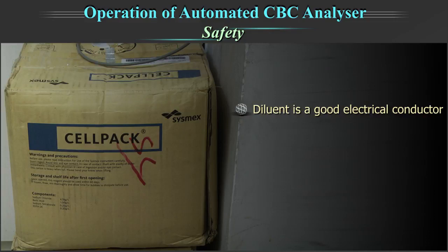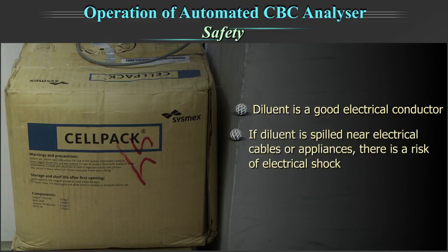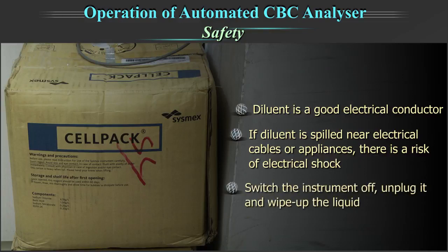Diluent is a good electrical conductor. If diluent is spilled near electrical cables or appliances, there is a risk of electrical shock. Switch the instrument off, unplug it, and wipe up the liquid.